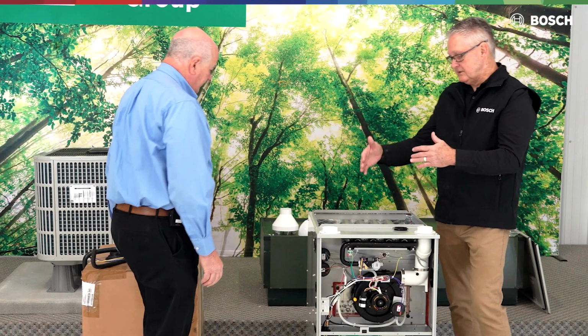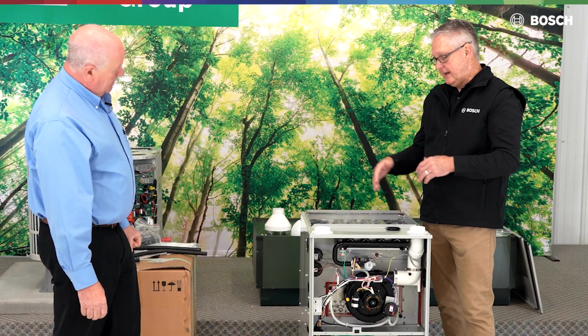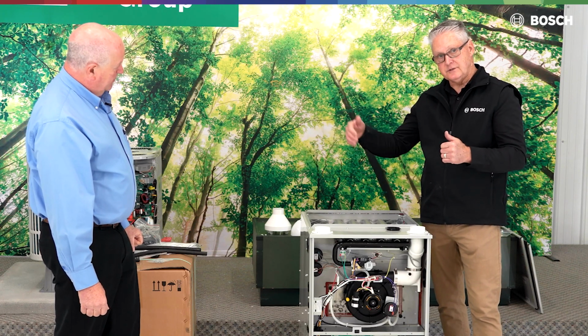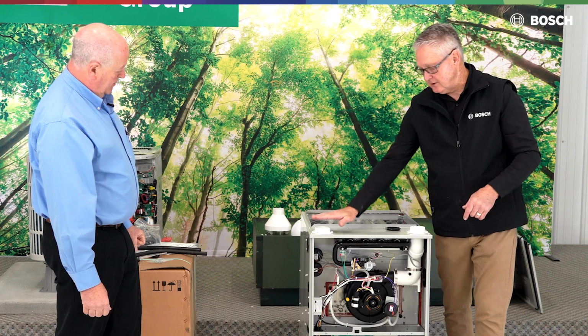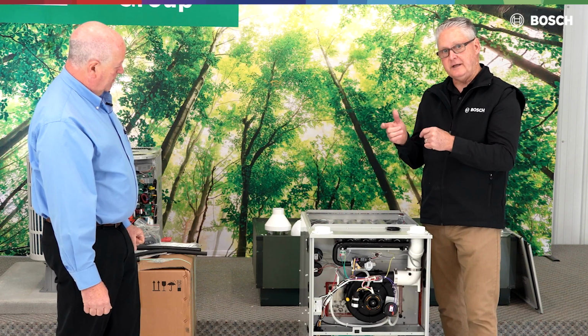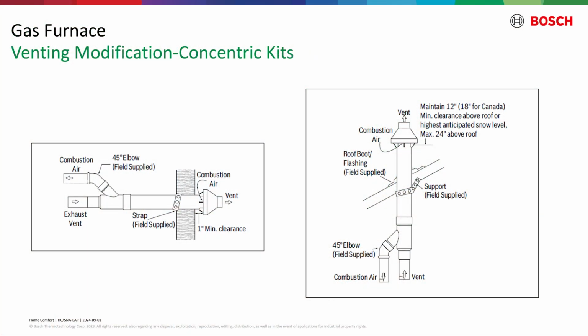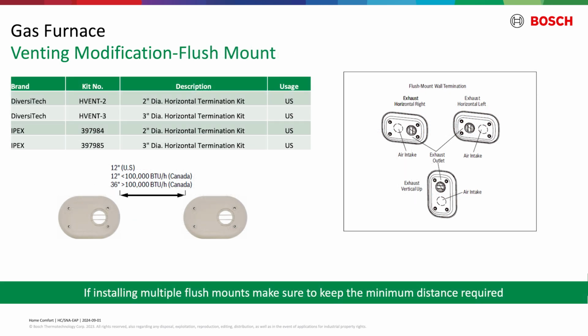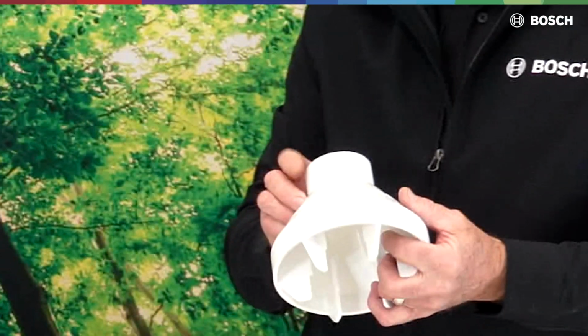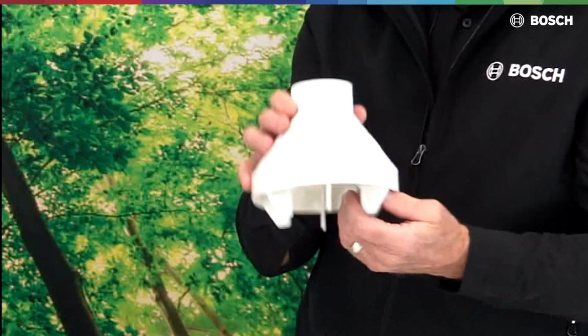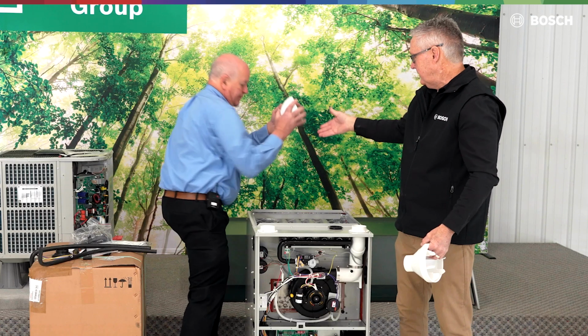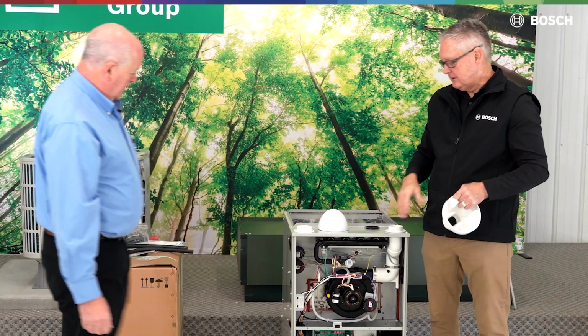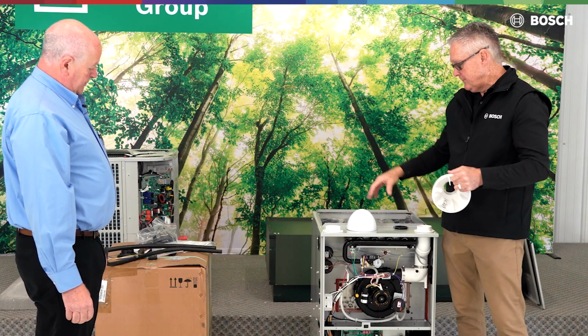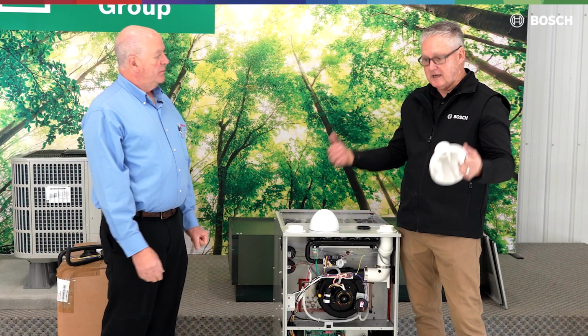So this is a 3rd generation Bosch furnace, and with this particular furnace, the IOM is going to state that I can take the bad gas and the combustion air, basically into a concentric fitting, going out and exiting the structure in that concentric fitting. We couldn't do that with the A style or the B style furnace, but now with this C model, we are able to do that. Literally what we're able to do is take a pipe within a pipe, if you don't mind, taking the bad gas out, sucking the combustion air in on the inside part of that, whether it's a cone looking like this, or a dome looking like that, or maybe a pancake style, but the concentric fitting is capable of working with this particular C style furnace now.